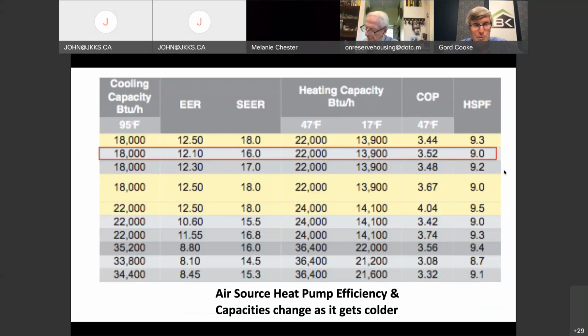Just as a little example of that, look at the red bar. This particular device has a nominal capacity of 18,000 BTUs, a ton and a half. Notice at 47 degrees Fahrenheit outside, its capacity is 22,000 BTUs, but as it gets colder out, its capacity drops. It only gets you 14,000 BTUs. So if your house has a heat loss of 22,000 BTUs on the coldest day, you'd need to put in a bigger heat pump in order to get this to work.